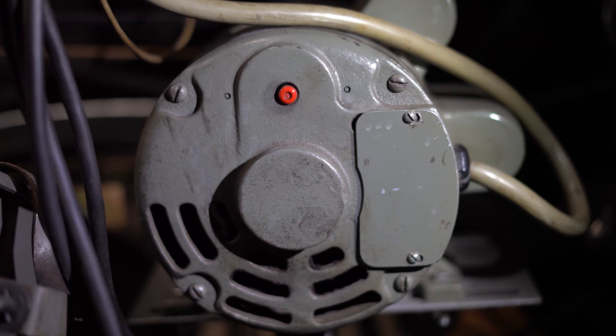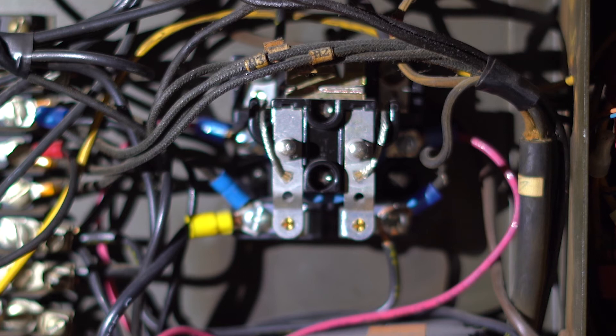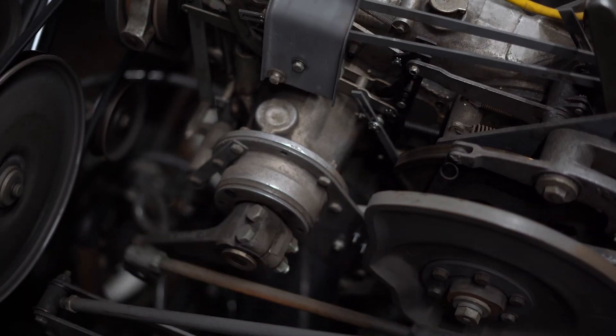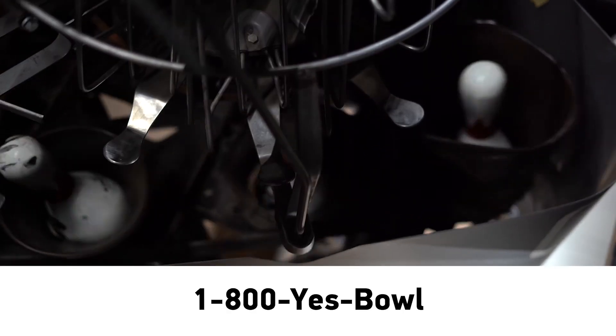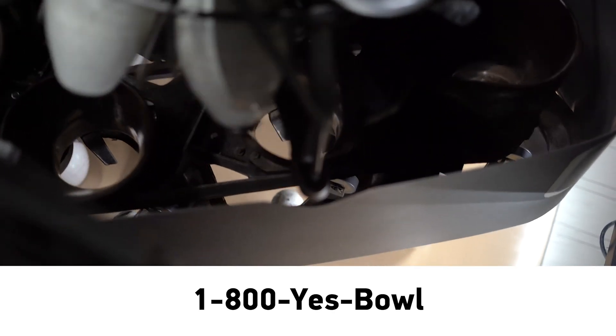In situations where you are installing a motor that is thermally protected into a pin setter with thermal protection in the contactor, it is possible to replace the old contactor with a newer contactor that does not require thermal protection. The instructions for how to do this are included with our replacement motor contactor part number 12-862-111-000, and you can always contact our tech support at 1-800-YES-BOWL if you need assistance along the way.